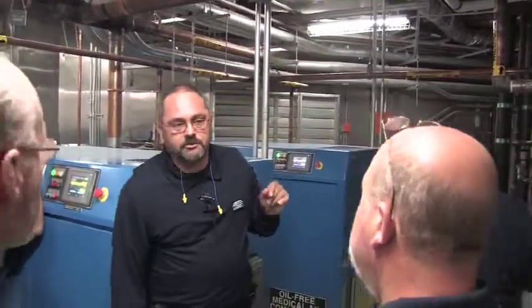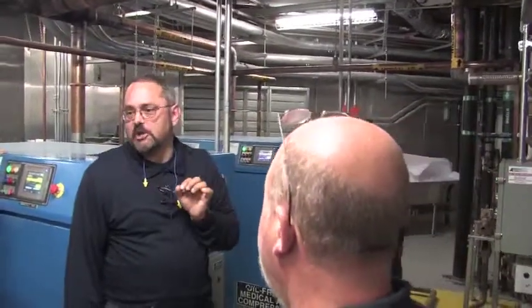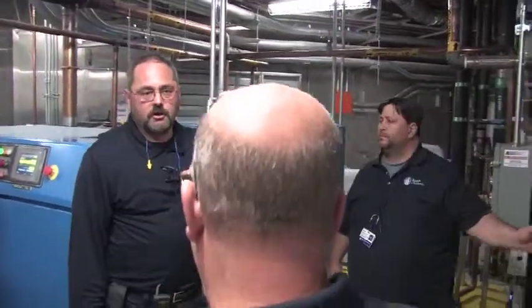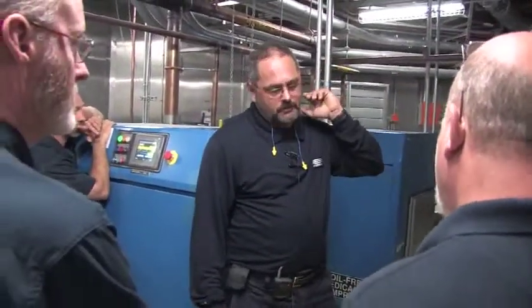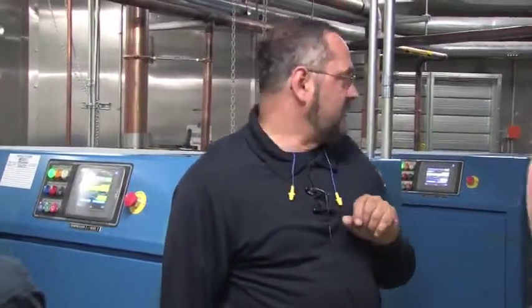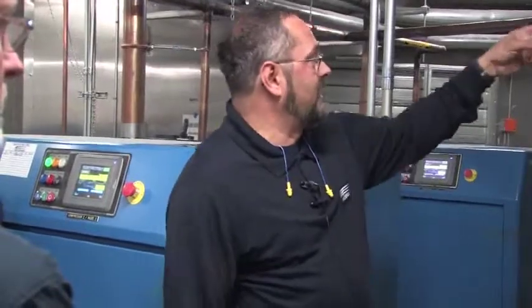Now the real key with the sequencer is it also looks at the rate of change. So if the pressure is inching down and it's at 91, where at 90 it's going to start a compressor, and suddenly the drain goes off or the dryer purges, and that transducer sees a 5-pound drop in half a second or a couple milliseconds, the sequencer sees how fast it's dropping. And if it drops 5 pounds in under like 2 seconds, it'll actually trigger a second machine. It'll trigger 2 machines to load and run.